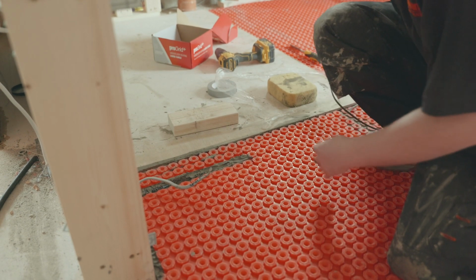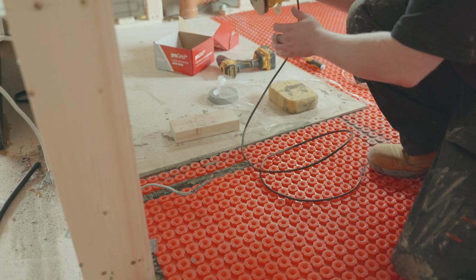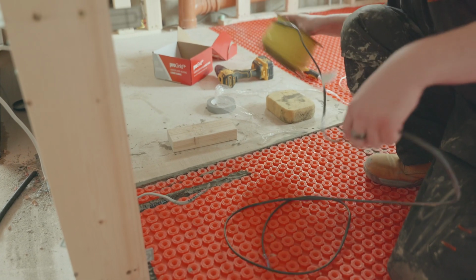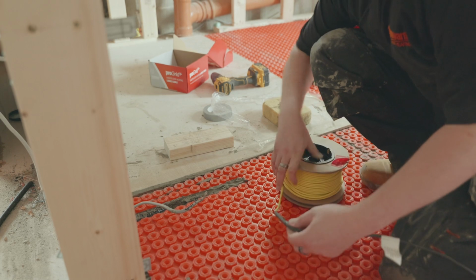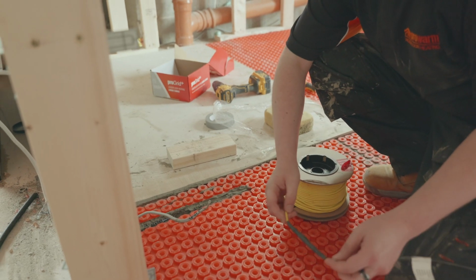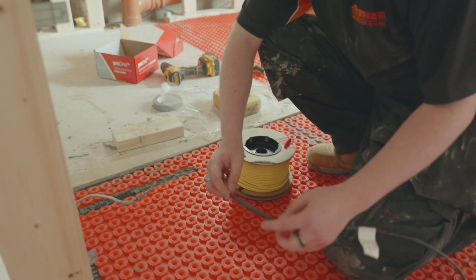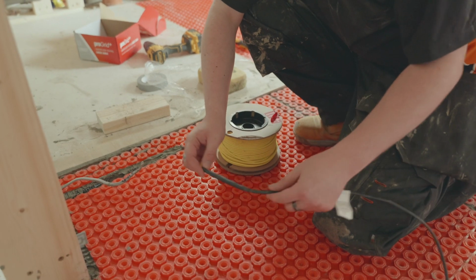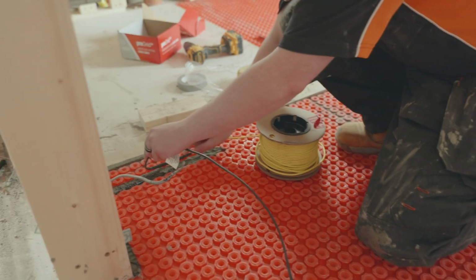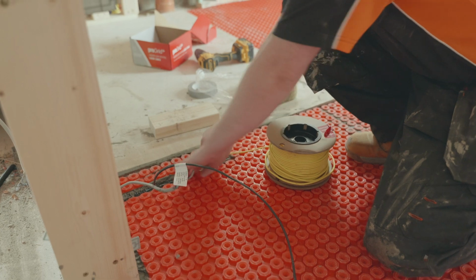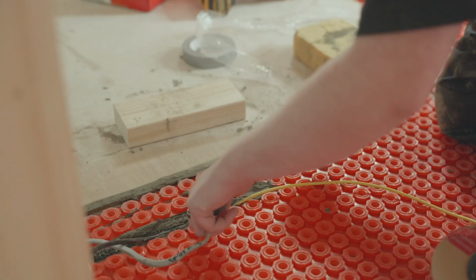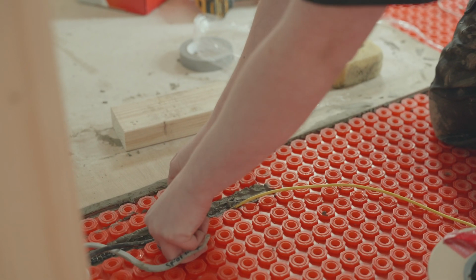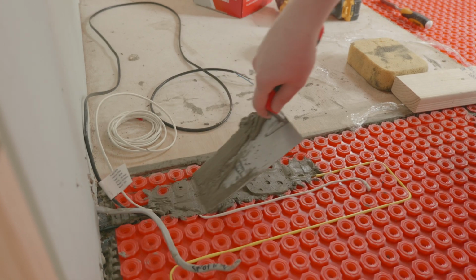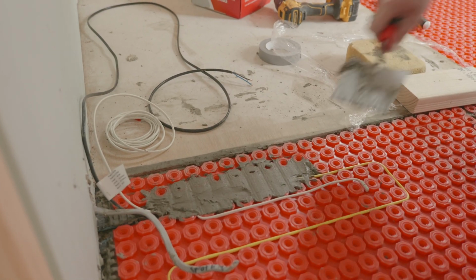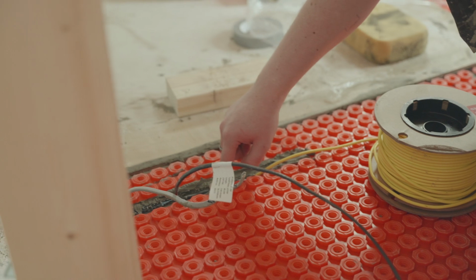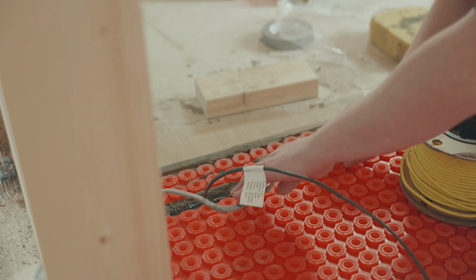Now, it's very important that when you install your cold tail, so this is the cold tail, and this is the heating element, and this is the cold tail joint. It's very important that this joint is fully encapsulated in tile adhesive or leveling compound, as if you don't do that, it's prone to overheat and that can cause your mat or your cable to fail.